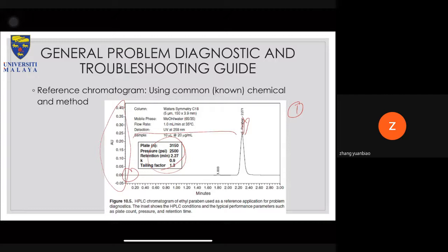So in the future, if you run into a problem, you might want to go back to your reference and do a comparison between your current data and the data that you ran initially. Because you know that this is the best, if say the plate number now becomes 2000 or 1500, then you know that your system is running at a maximum of 50% of what it was previously capable of. So you might want to do some servicing, or perhaps change some components or modules of your HPLC, so that you can reuse it once it is fixed.